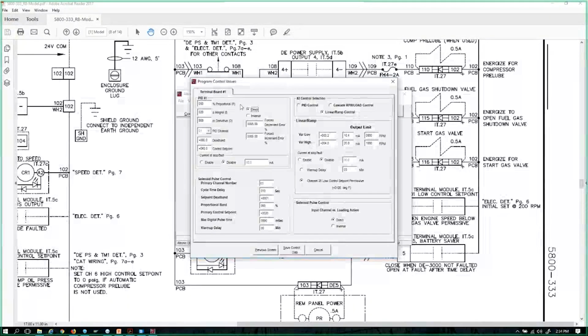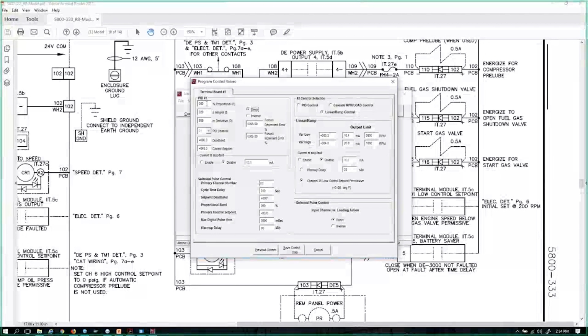So again, I'm going to let you go out and look at some of the sources I mentioned earlier if you want to learn more about this. But I'm going to tell you at 120, this thing's going to be so slow and so unresponsive, you're going to have problems. 50 is my default go-to. If I'm using this for a suction control valve or a recycle valve, pneumatically controlled through an I2P regulator, I'm going to be using 50 as my go-to default.